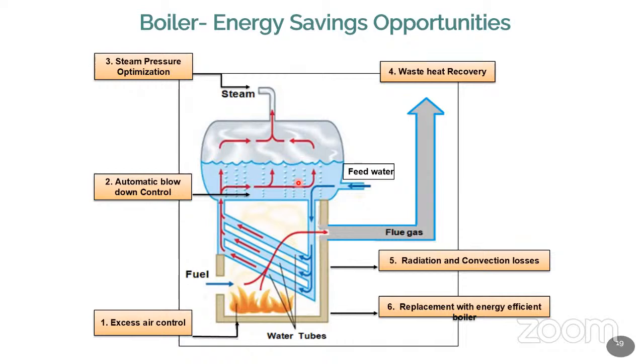Now if you heat the water and start producing steam, at one stage the TDS level of the water inside the boiler will keep increasing. When the TDS level keeps increasing, you should take the water out and not use it, and you can add fresh water. That is called blow down. At regular intervals, you can do the blow down. Blow down means you let out the water, not all of it, but 60%, 70%, or 30% depending on the TDS level, the total dissolved solids in the system.